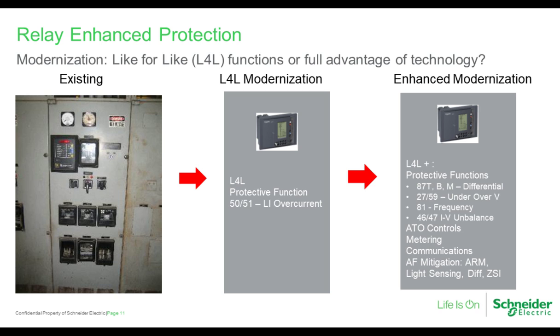With a new solid state, like for like, we can get the same protective functions of that existing, and now we're able to consolidate multiple relays on a door to one single device, saving some valuable space and other components to be integrated. So now we see that we've got that same 50-51, but now in one relay instead of 3 individual single-phase relays. We can also enhance that by adding more protection functions. Not only is it like the existing mechanical relays, but now we can add some additional protective functions and also communication.